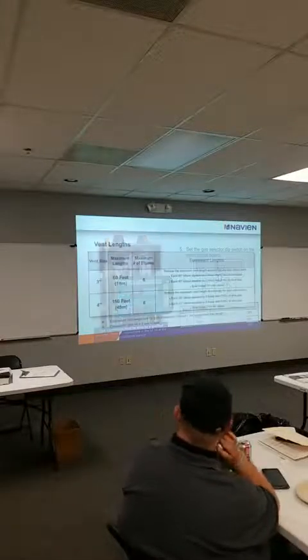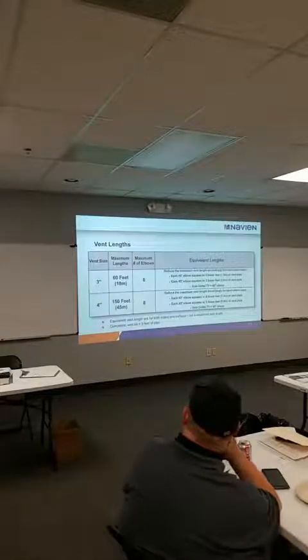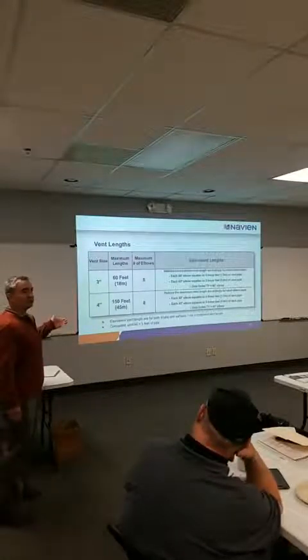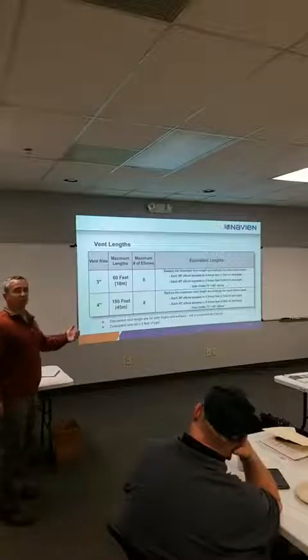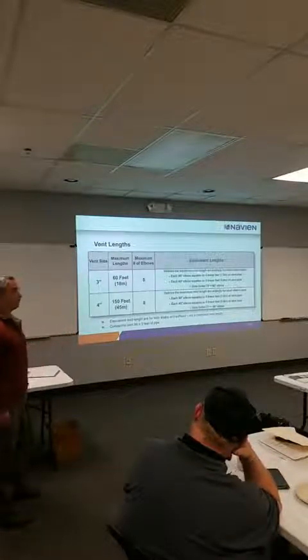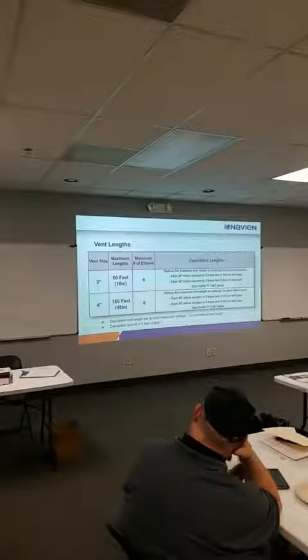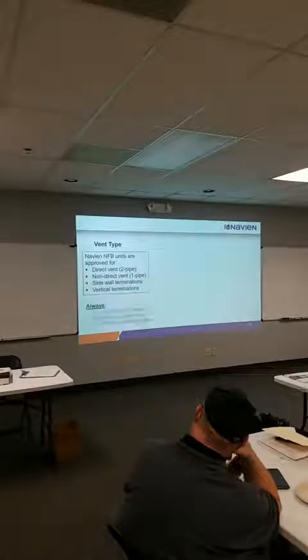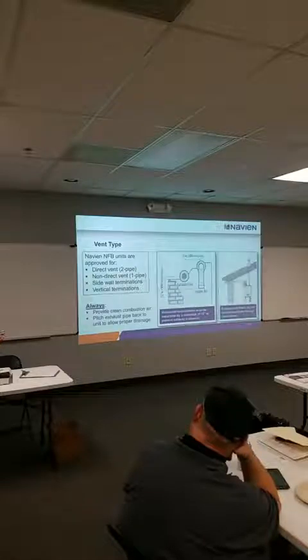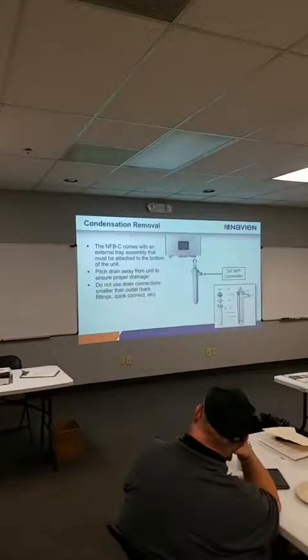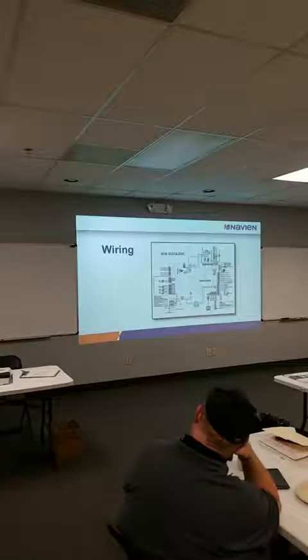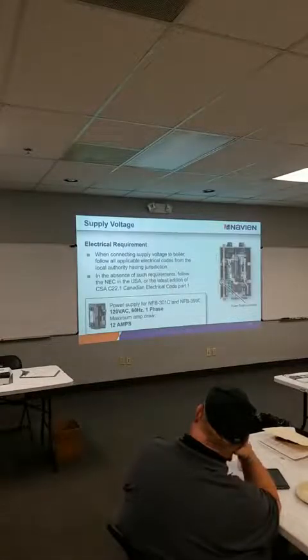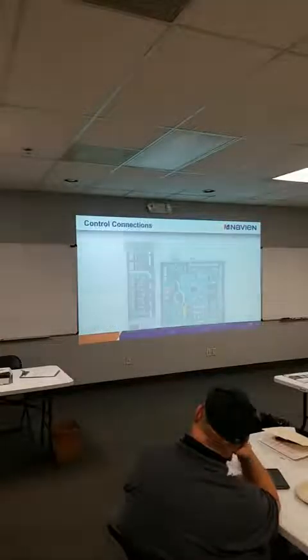The computer board looks the same, it's just a little different, but your LP conversion again is number 1 on the second bank. The venting on this is gonna look similar, but it's 3 and 4 inch instead of 2 and 3 inch. All the other rules apply, they're identical. So in all the same venting pictures, it's approved for room makeup air. That's the condensate trap. So this board is a little different than the old board, or the other boards.